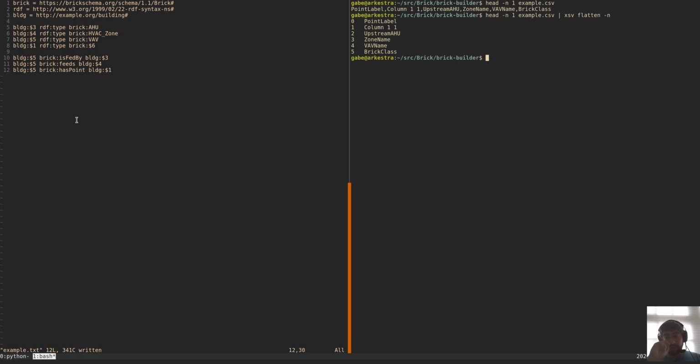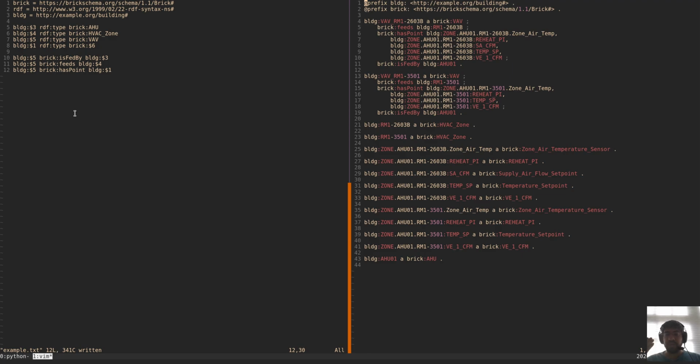What we're going to do is take the top 10 rows of the CSV file, just to have a smaller example, and apply the BrickBuilder tool, which is make.py. That's going to take an argument, which is the name of the template, in this case example.txt, and the name of a CSV file, top10.csv.